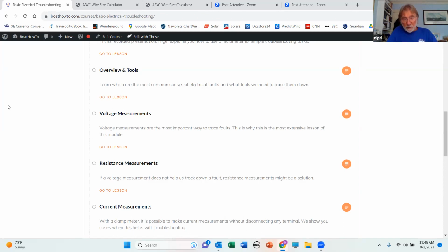You can potentially get into trouble if you're not used to using a meter. So I tell people, absolutely, if you're a novice with a meter, just stick in the volts mode and make sure you've got AC and DC volts, and ideally have separate switch positions for that. Because a lot of meters have a common switch position and then you have to toggle between AC and DC, and you've got a tiny little LCD screen and an even tinier little DC and AC symbol, and it's very easy to be in the wrong mode and not realize it. So we want to be able to measure that.